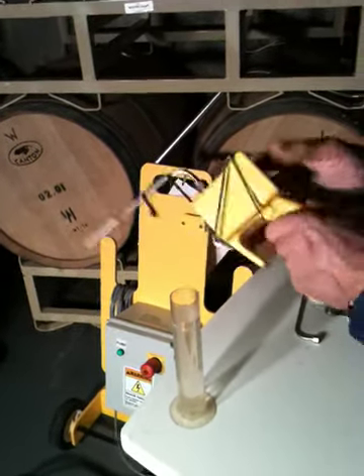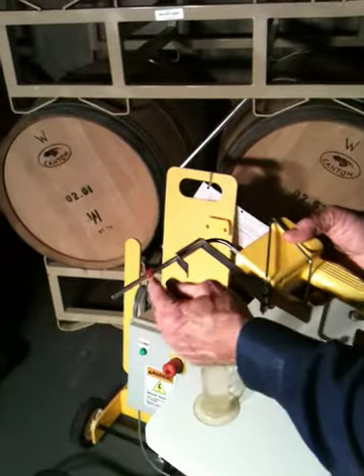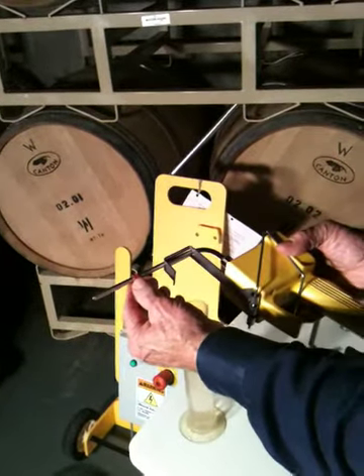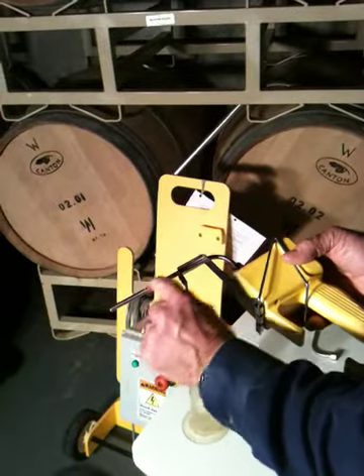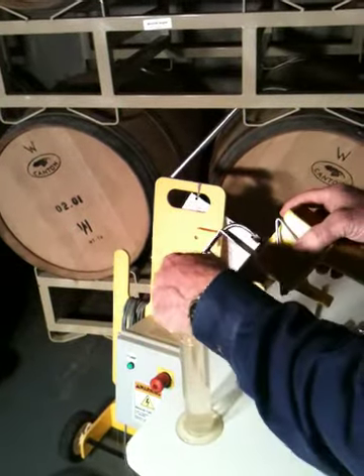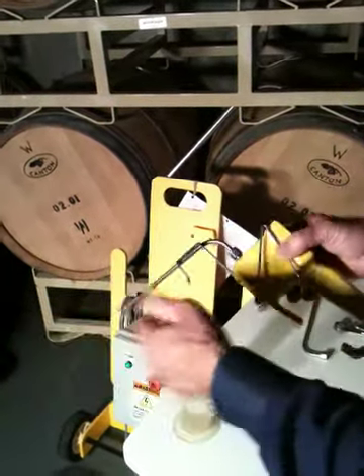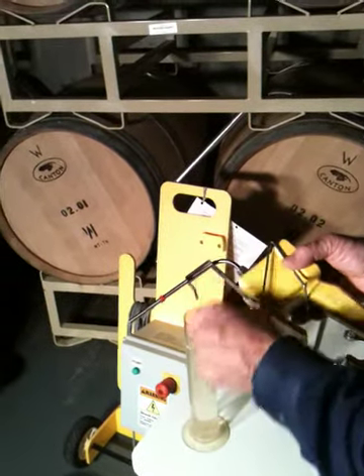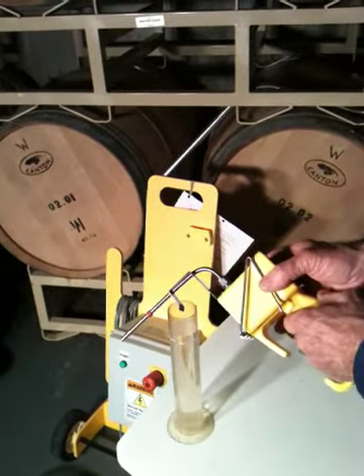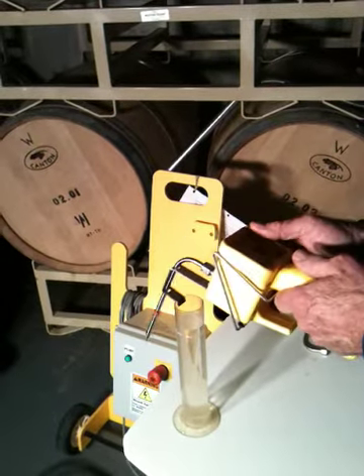It's very, very simple. All this band is used for is to indicate what your level is you have it calibrated to. If you want to calibrate it 1 inch from the tip, you slide the band to 1 inch down, recalibrate it to that level, it's a done deal. If you want to raise it up 1 inch, slide it up 1 inch, recalibrate to that level. No problem. Okay, so let's do a leak test.